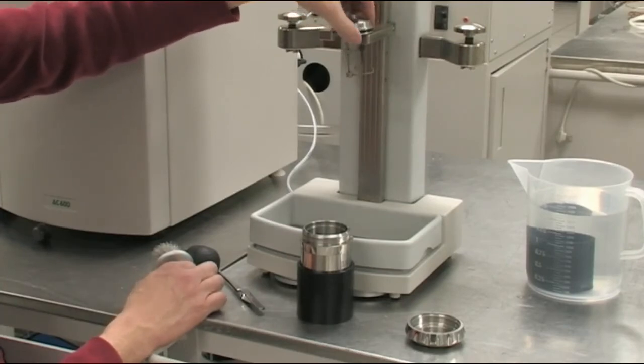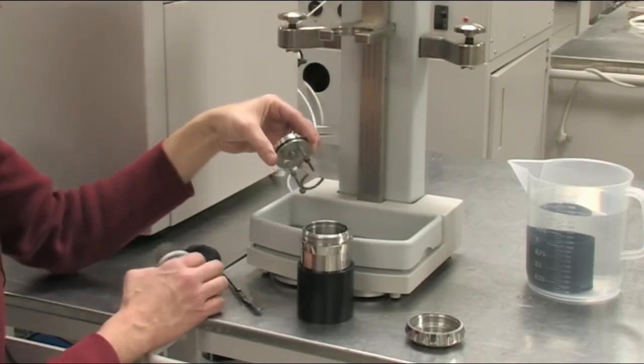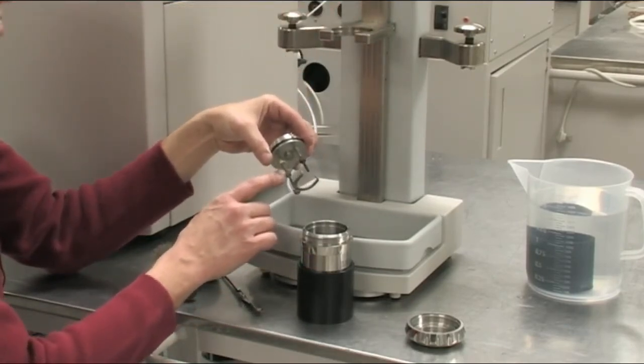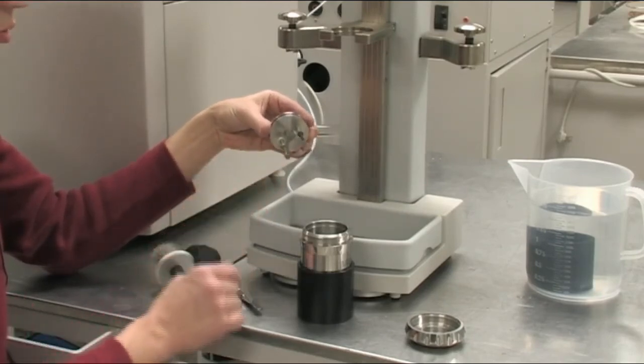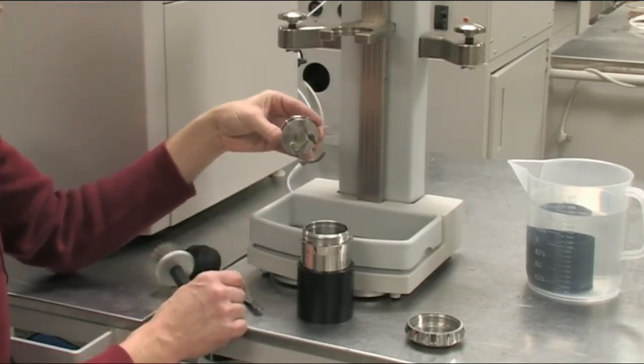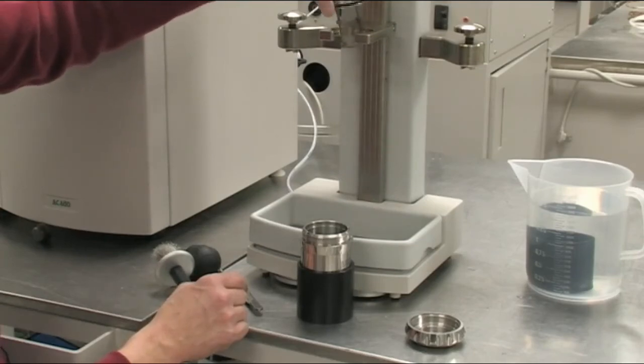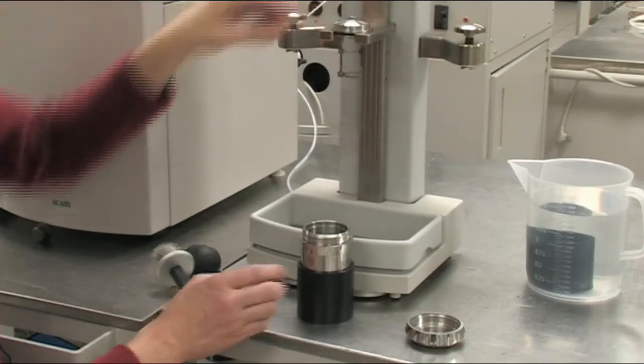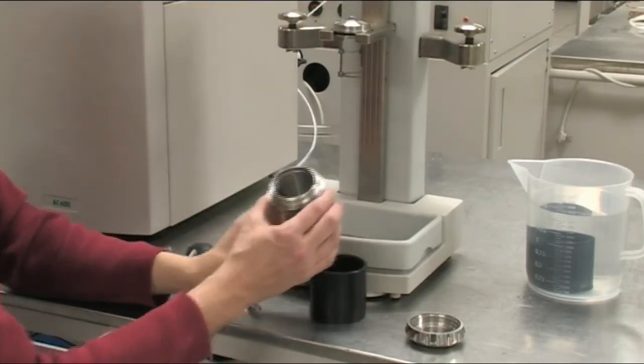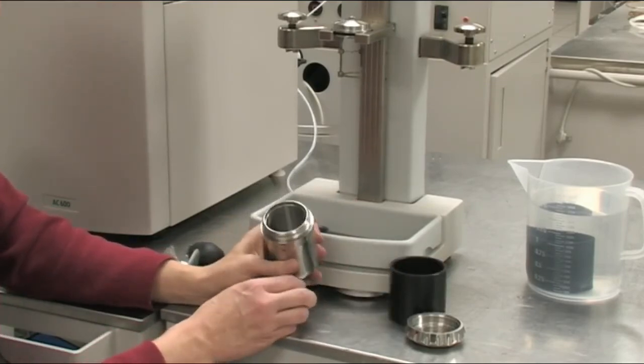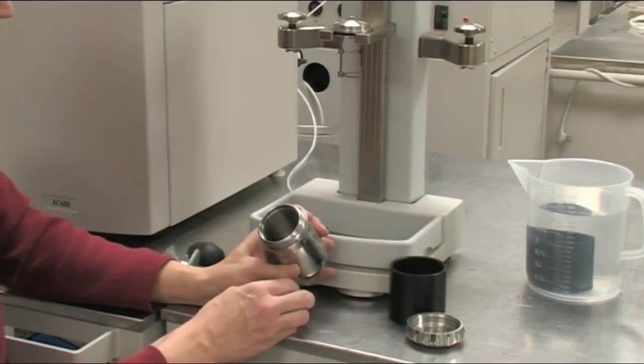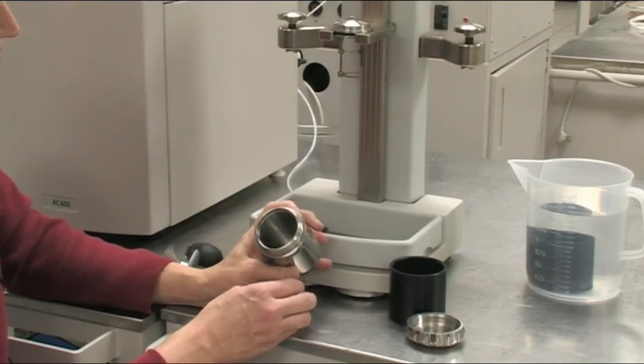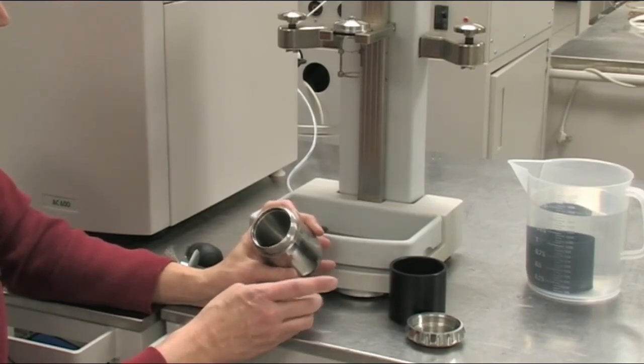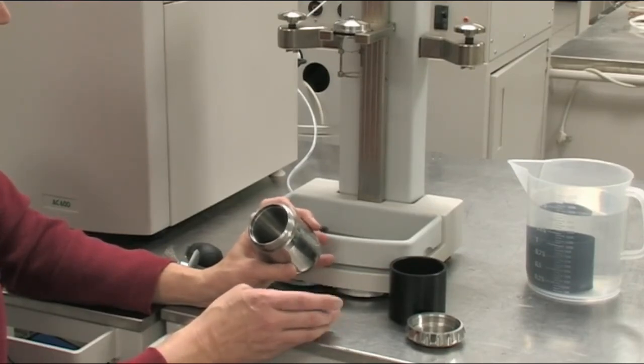The igniter you want to inspect to make sure nothing is broken as far as the wire, and also rinse it off with water. Depending on if you're going to analyze the residue, you're going to rinse out the inside of the vessel thoroughly. If not analyzing the residue, you want to thoroughly rinse out the vessel for the next use.